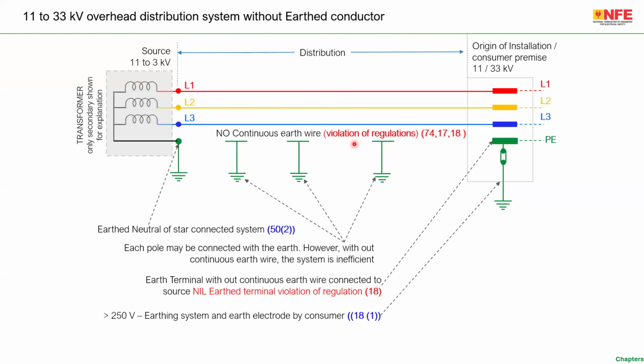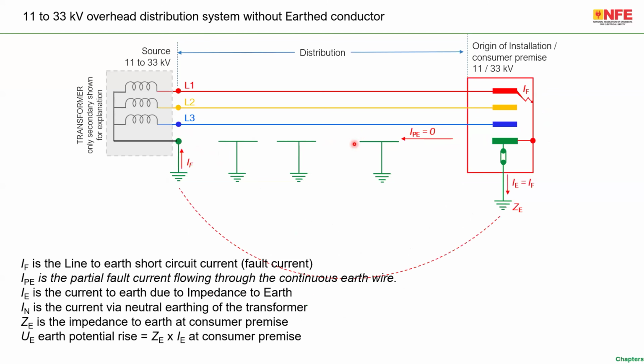This is not new. These have been in the regulation for decades, and in the standards for decades. Under this condition, imagine there is a fault, IF. There is no metallic fault return path, so I put IPE as 0. The entire IE equals IF. IE, the current flowing through the earth electrode, is the total fault current.